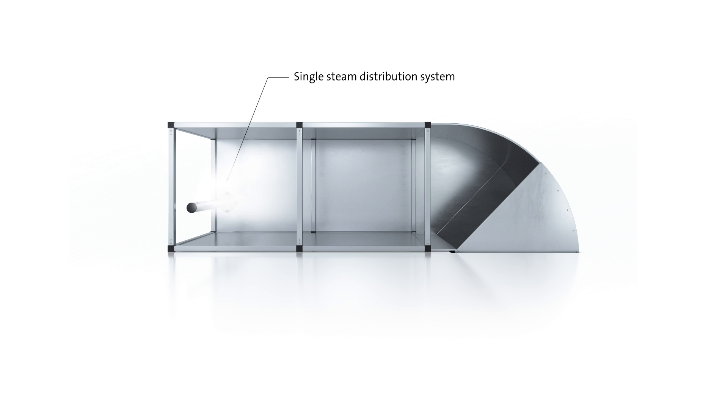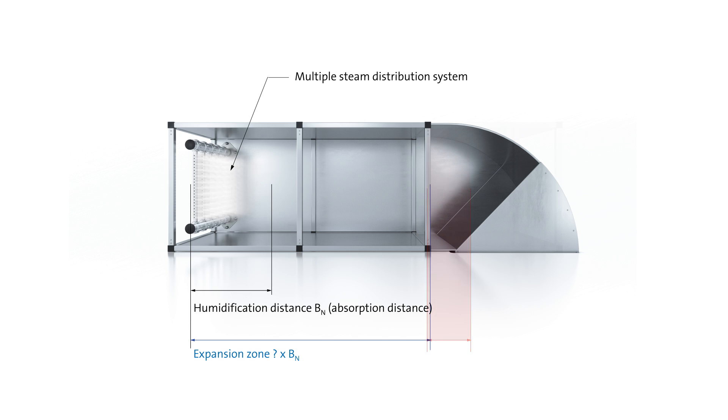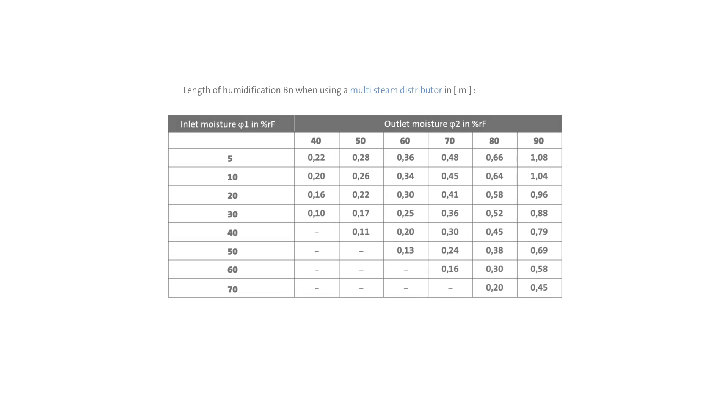If the available humidification distance is insufficient, the necessary distance can probably be shortened by a more homogeneous steam distribution, effectuated by a multiple steam distribution system. If the relative humidity of the inlet air amounts to 10% and the relative humidity of the outlet air is 50%, the necessary humidification distance is now reduced to 26 cm.